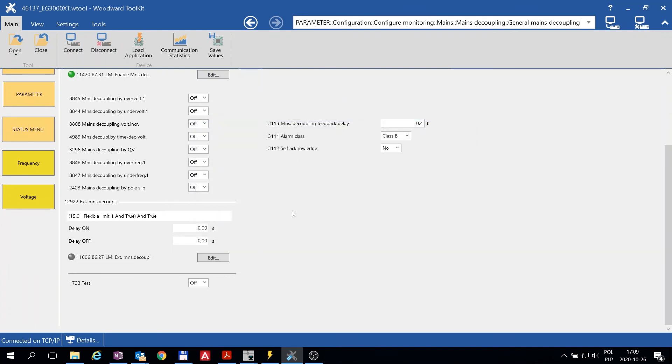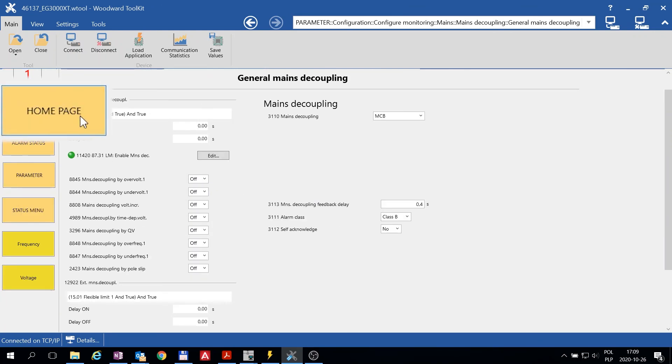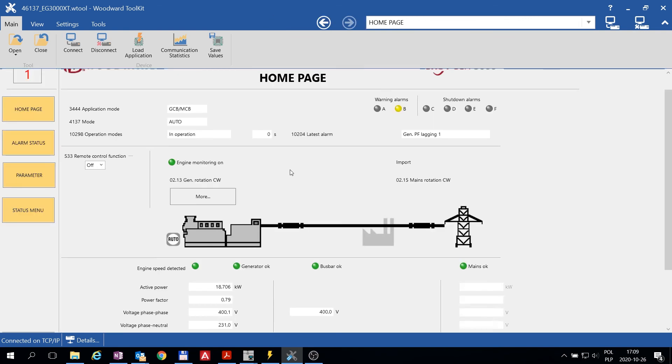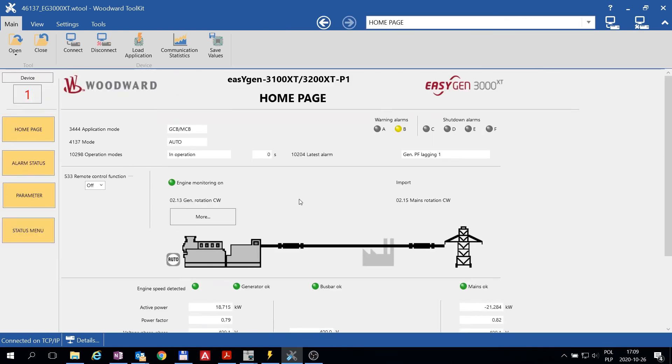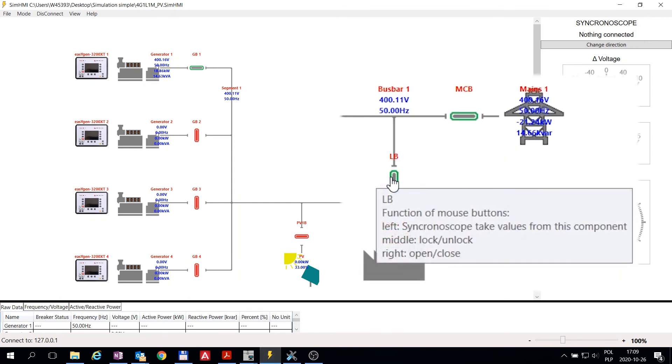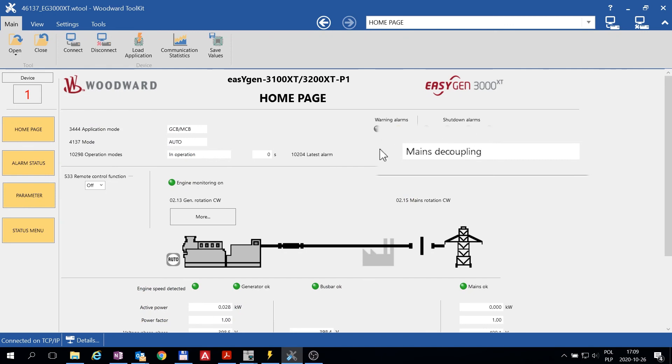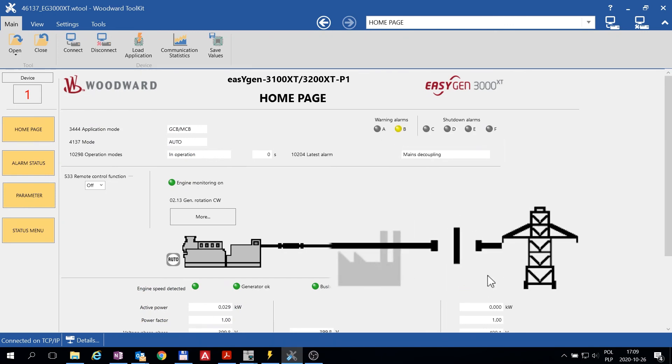And now, we can do some testing. Let's open the Load Breaker. As you can see, the EasyGen opened the MCB as soon as it saw export power.